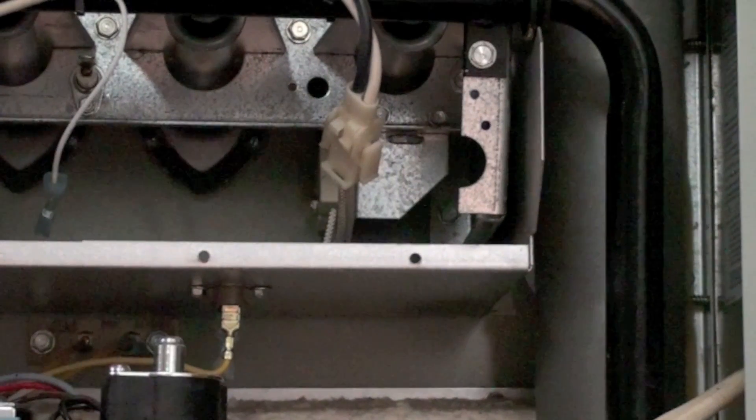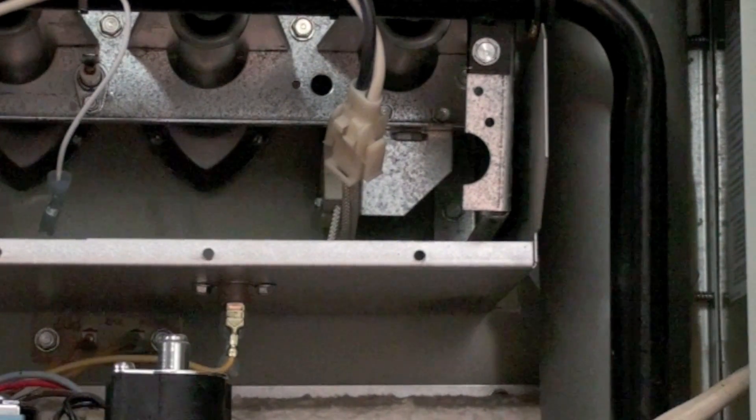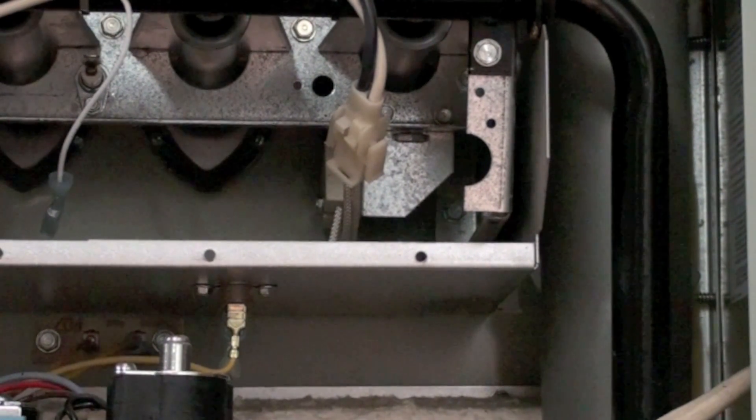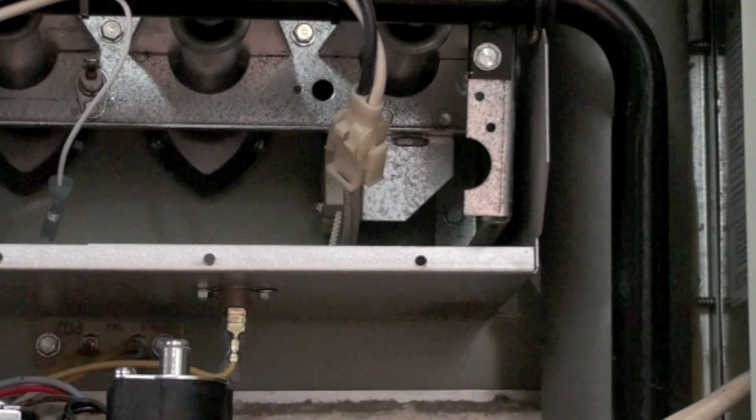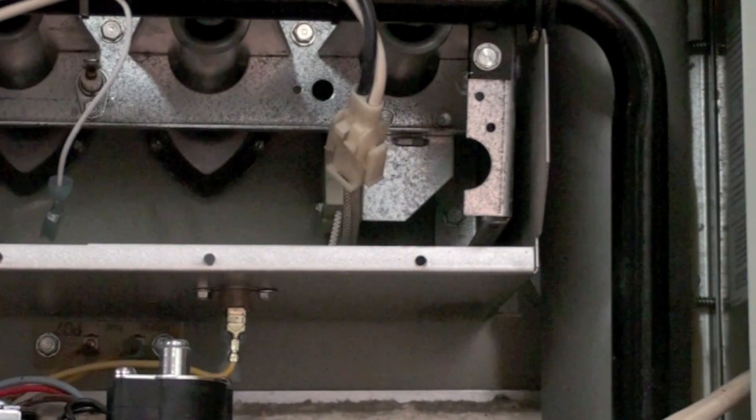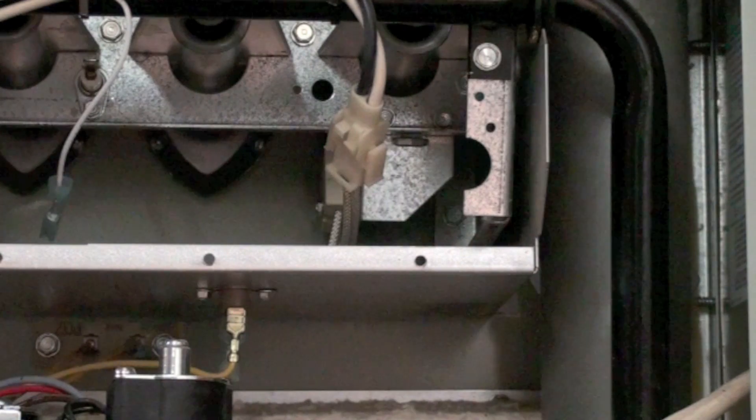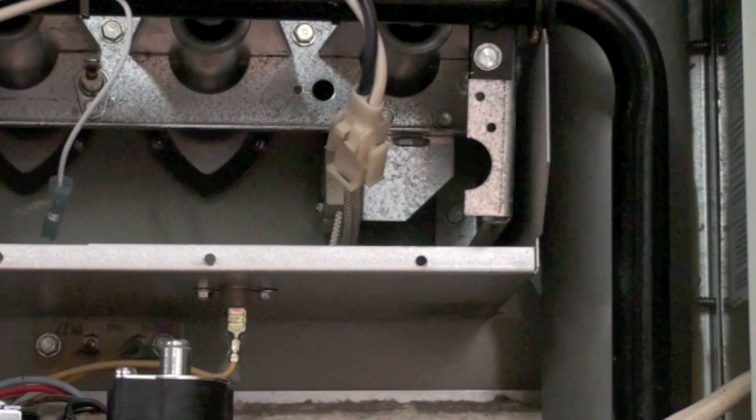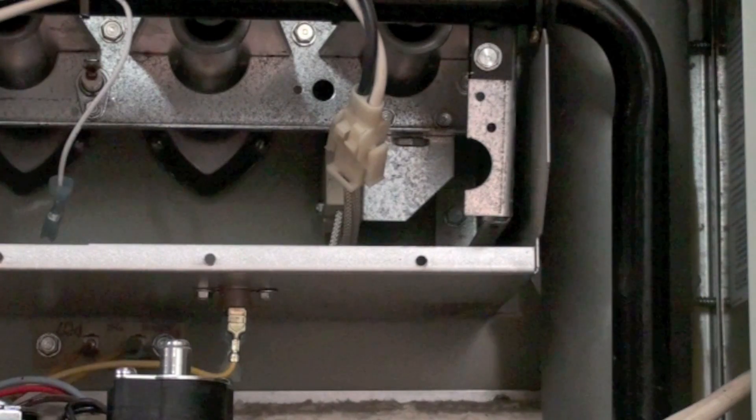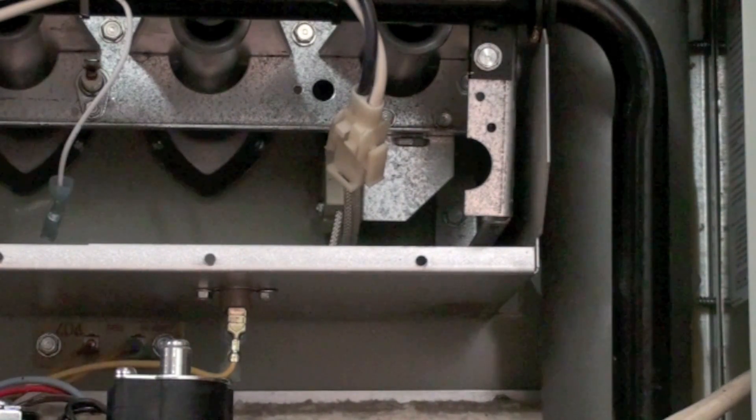So if you have the symptoms that you get a glow on one side of the furnace, the burners light and then they shut off and it does that several times, pull out the flame rod, clean it up, put it back in.